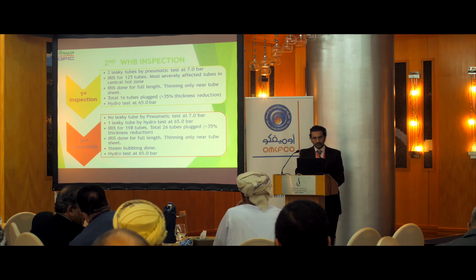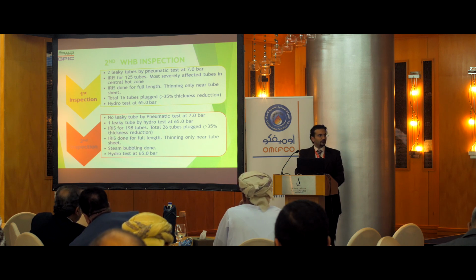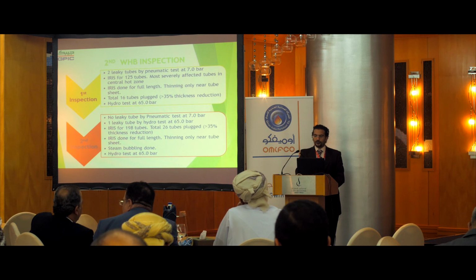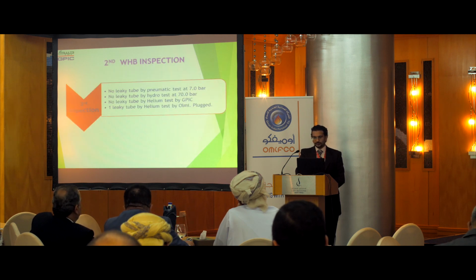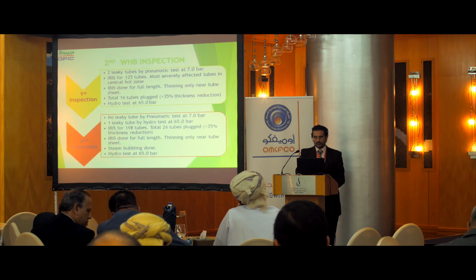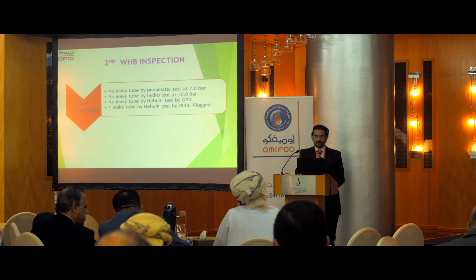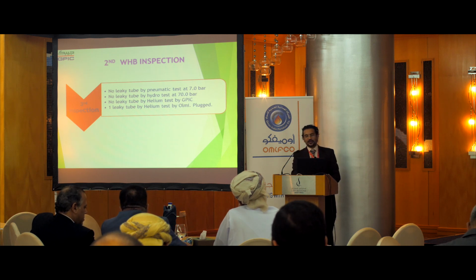Second inspection, there were no leaky tubes, and we did the internal rotational inspection for the full length. There was only thinning near the tube sheet. Steam bubbling was done, and the hydro test. Actually, there was one leaky tube at 65 bar. And the third inspection, also no leaky tubes until we did the helium test, and we found one leaky tube.